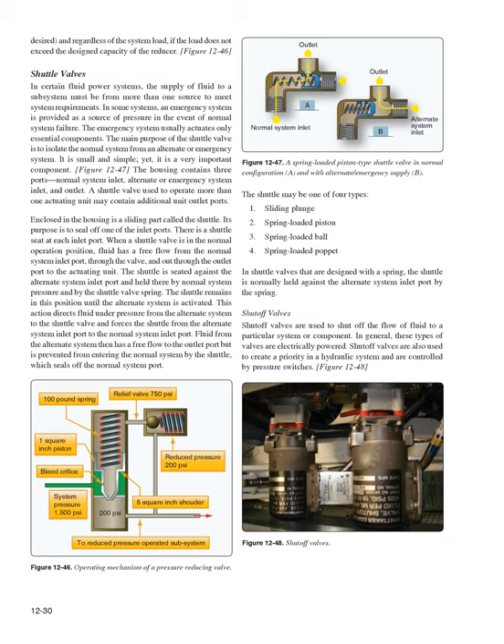Figure 12-47. The housing contains three ports: normal system inlet, alternate or emergency system inlet, and outlet. A shuttle valve used to operate more than one actuating unit may contain additional unit outlet ports. Enclosed in the housing is a sliding part called the shuttle. Its purpose is to seal off one of the inlet ports. There is a shuttle seat at each inlet port. When a shuttle valve is in the normal operation position, fluid has a free flow from the normal system inlet port, through the valve, and out through the outlet port to the actuating unit. The shuttle is seated against the alternate system inlet port and held there by normal system pressure and by the shuttle valve spring. The shuttle remains in this position until the alternate system is activated.